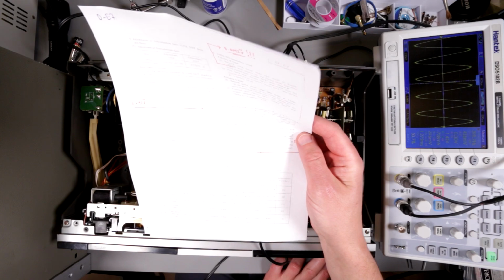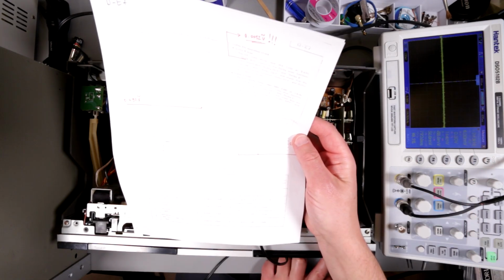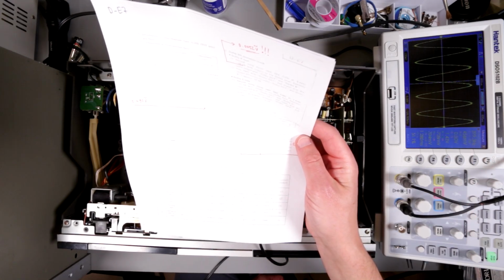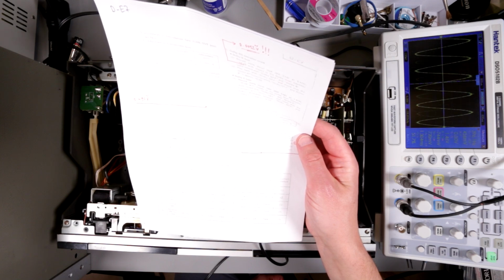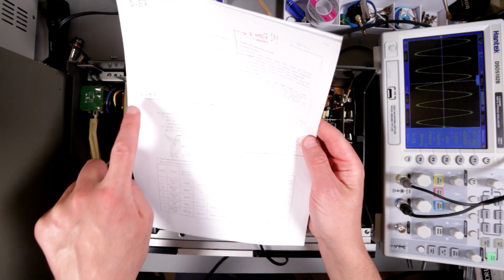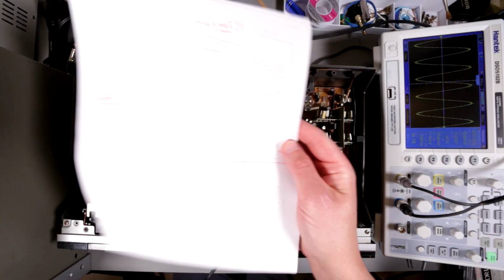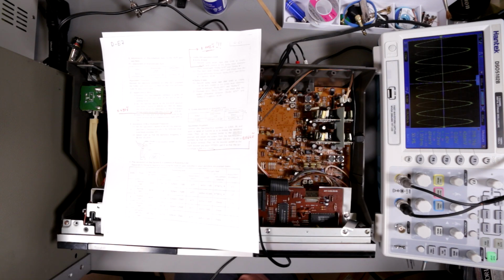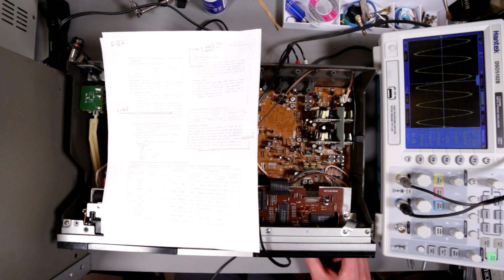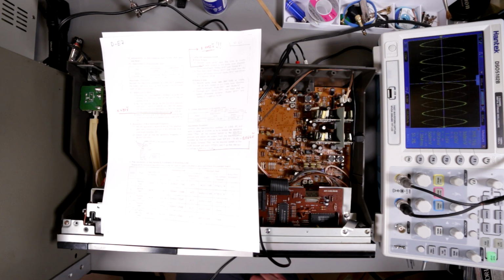Yes, it is in source position right now, hence you see the signal here, otherwise you won't see anything. Okay, adjust the meter using the attenuator so that the output voltage at line out is 500 millivolt minus 0.5 dB, which is 0.49 volt RMS. So let's just adjust it using the attenuator right here on the function generator. 490 millivolt. I think 488 is pretty good.